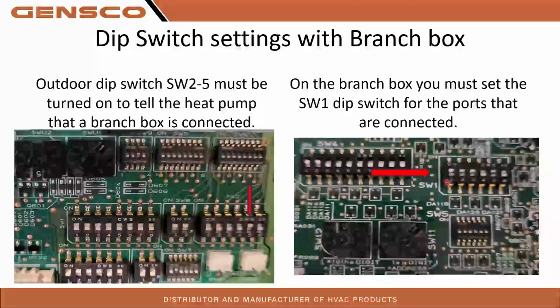But otherwise, what you're going to do is, like I said, if you have a 5-port branch box, and let's say for this example here, we're using ports A, B, C, and E, then we turn on switch 1, 2, 3, and 5, like what you're seeing right here. So D port's not being used, switch on that stays off. And it can be any combination of those. So depending on which ports you're using, that's what you're going to set here.